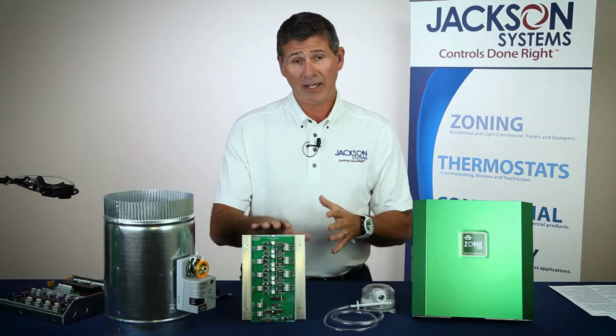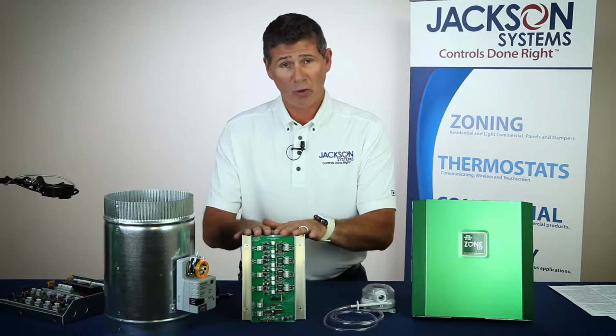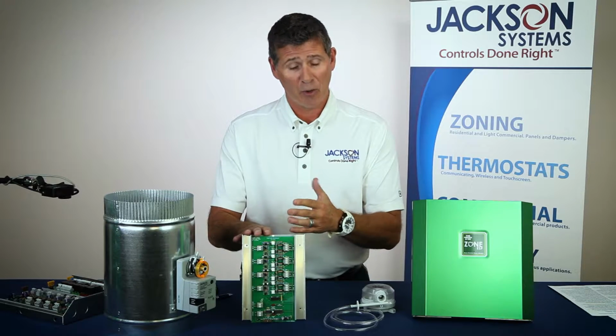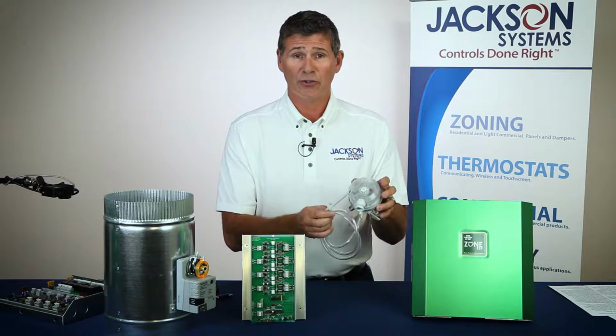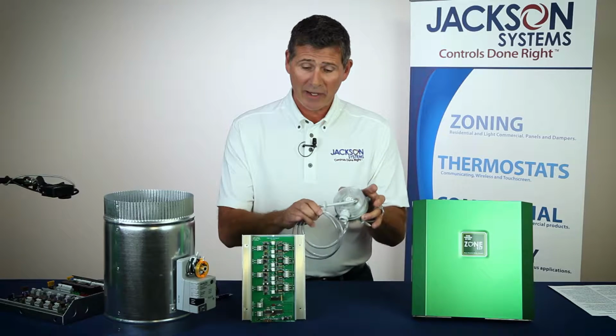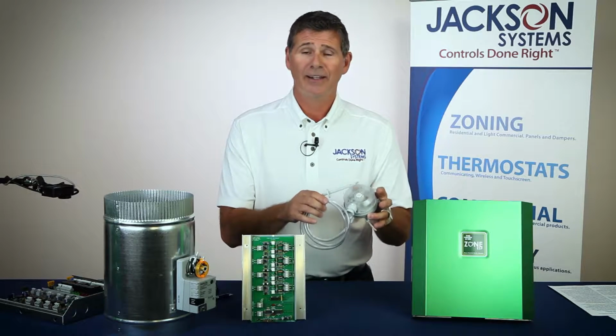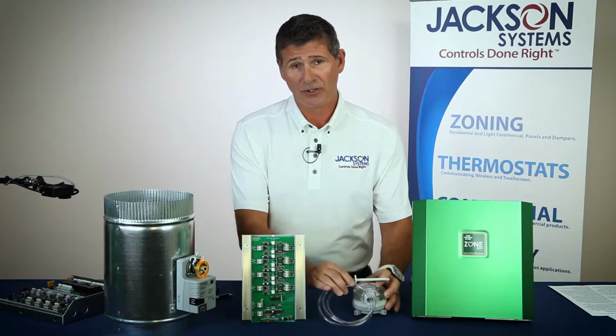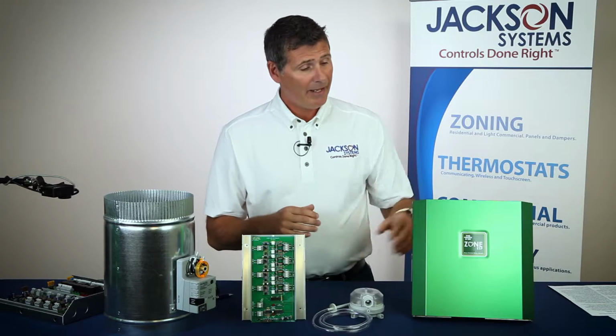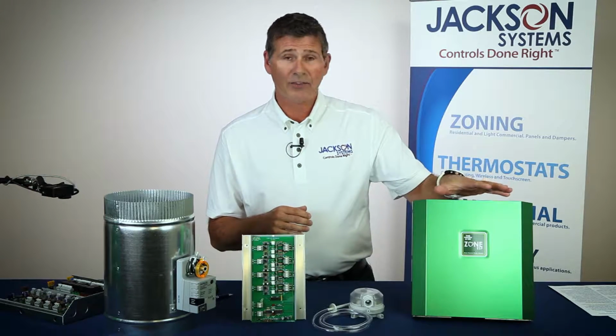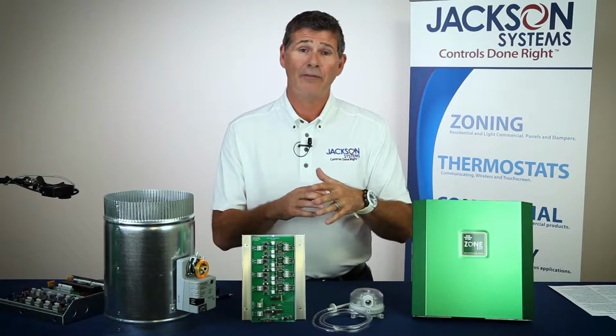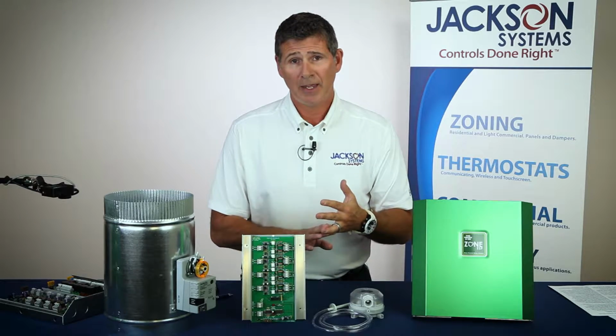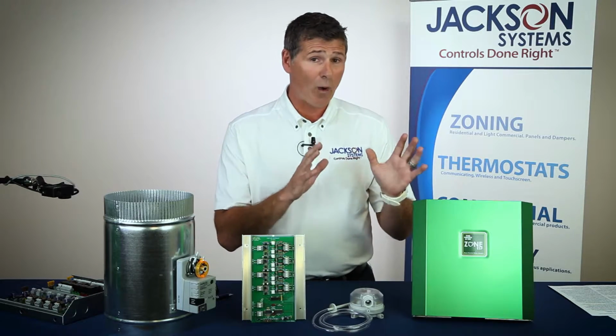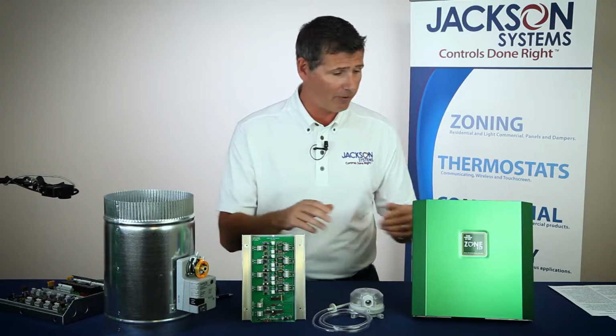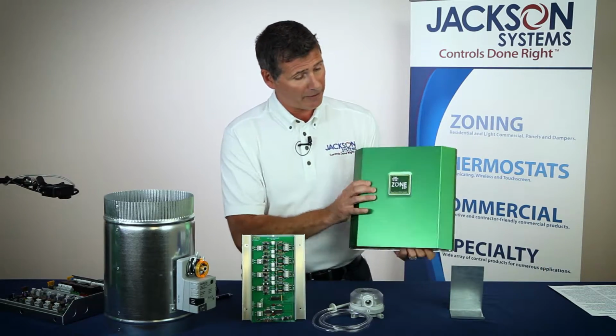Right in front of me here I have the actual ESP board of the control panel itself, and I'll take you through that here in a moment. And I've also got a static pressure control sensor which works with the control panel itself that constantly monitors the duct pressure inside the system. And then of course the other way that we sell it is as a combined system where you have either our 2 or our 3 zone panel built in conjunction with and wired right here ready to go with the panel. I can show you the inside of that a little bit here.